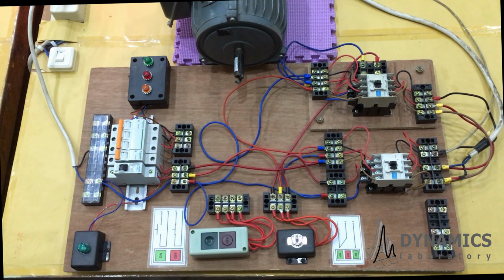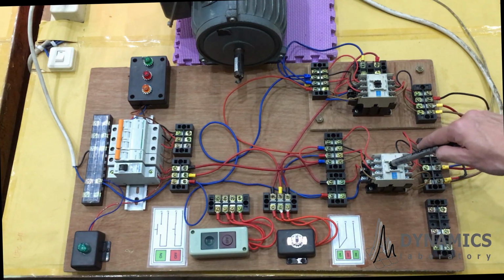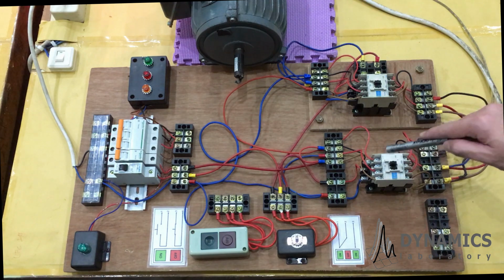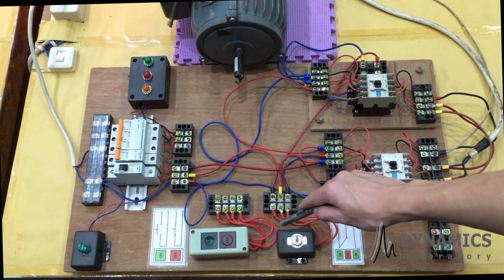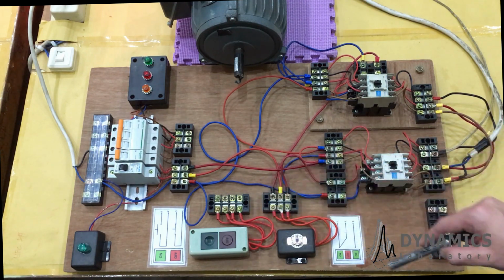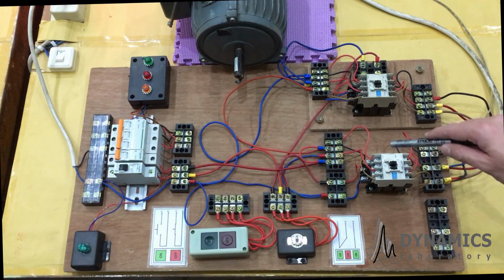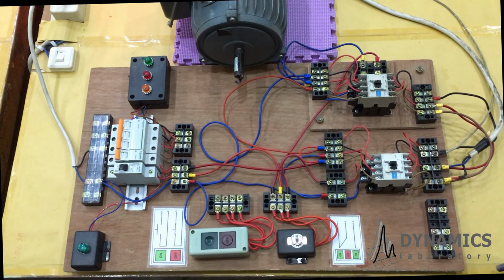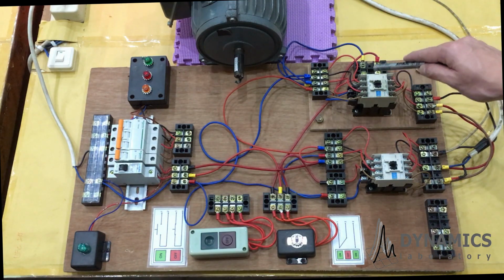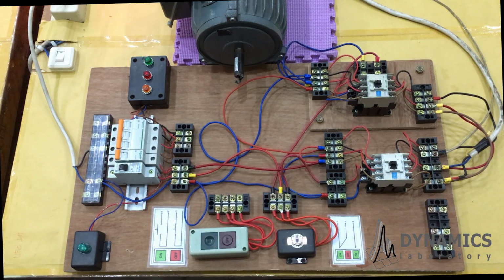Second load circuit. In this circuit, we want to reverse the rotational direction of one-phase AC motor. Therefore, we will utilize two contactors. And we have to use switch control circuit. For example, contactor 1 for counterclockwise rotational direction. Meanwhile, contactor 2 for clockwise rotational direction. Let's see the circuit.